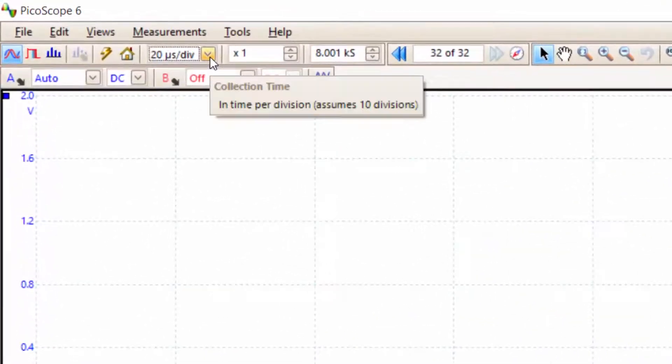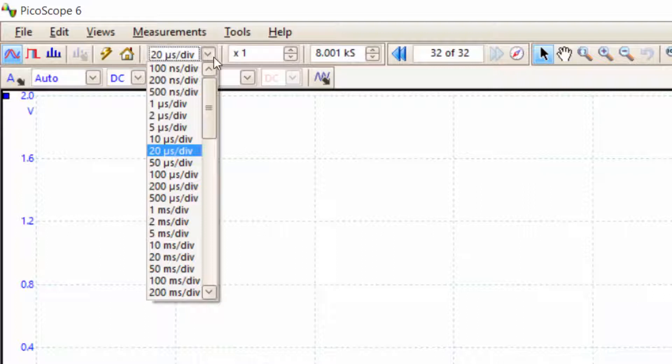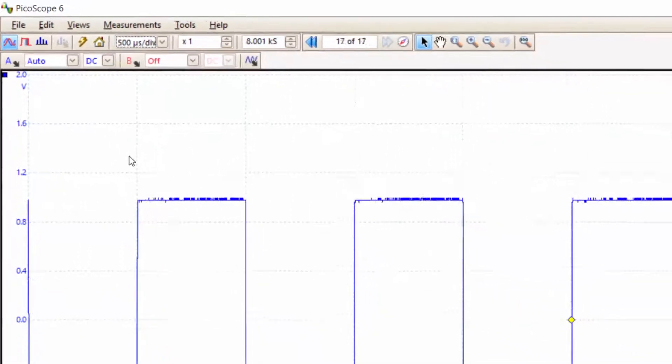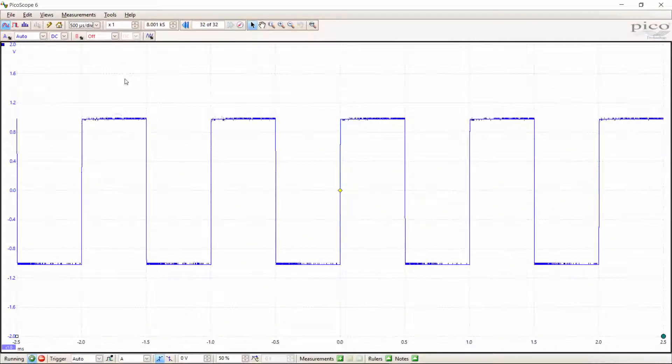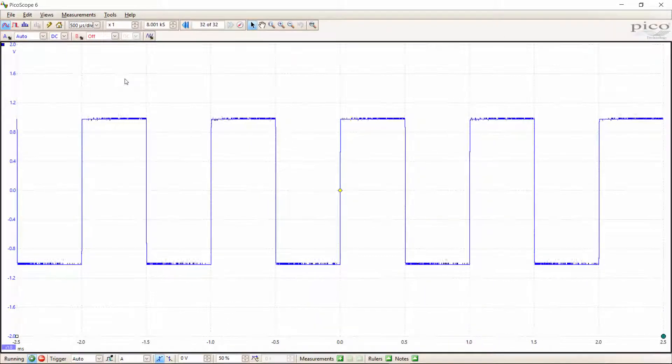We can do so by going onto the menu up here, which allows us to select the number of seconds or microseconds per division that we want for our waveform. Since we have a one kilohertz waveform, let's set the scale to 500 microseconds per division. Then you can see that a reasonable number of periods is displayed on our screen.